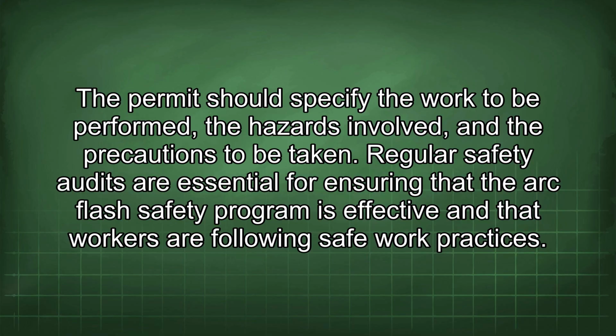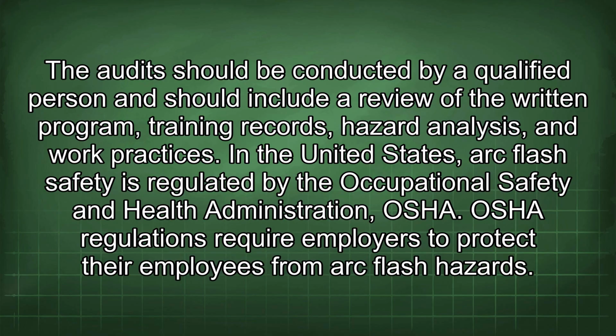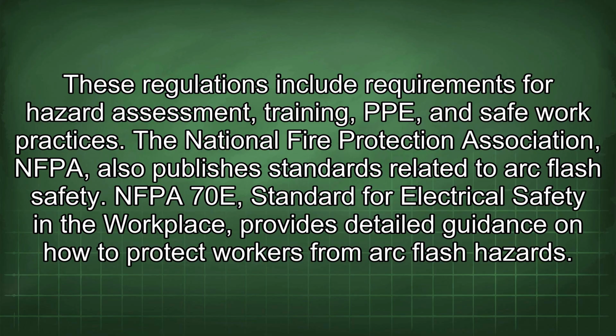Regular safety audits are essential for ensuring that the arc flash safety program is effective and that workers are following safe work practices. The audit should be conducted by a qualified person and should include a review of the written program, training records, hazard analysis, and work practices. In the United States, arc flash safety is regulated by the Occupational Safety and Health Administration (OSHA). OSHA regulations require employers to protect their employees from arc flash hazards. These regulations include requirements for hazard assessment, training, PPE, and safe work practices. The National Fire Protection Association (NFPA) also publishes standards related to arc flash safety. NFPA 70E, Standard for Electrical Safety in the Workplace, provides detailed guidance on how to protect workers from arc flash hazards.